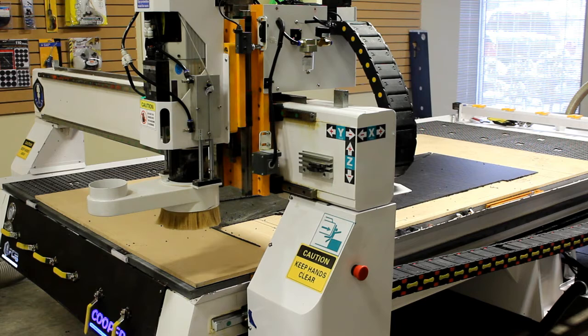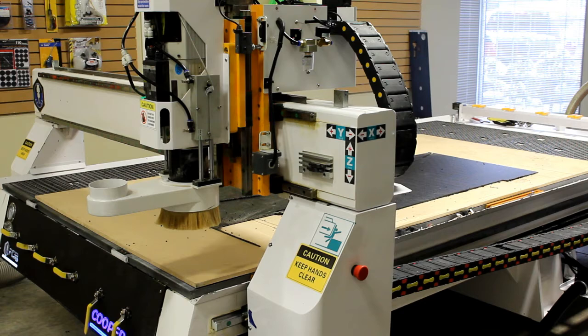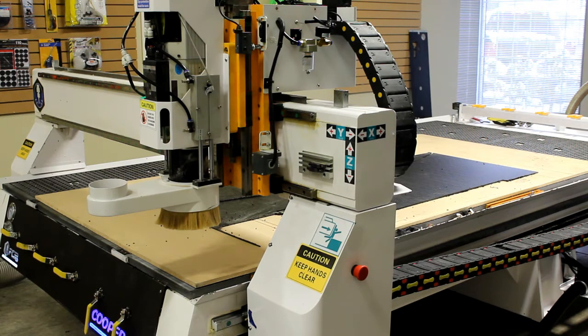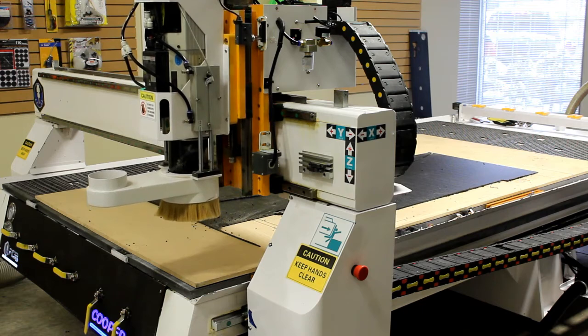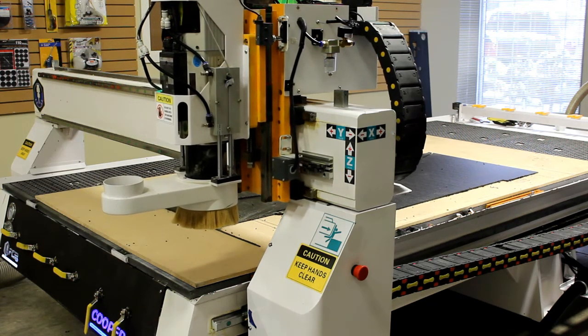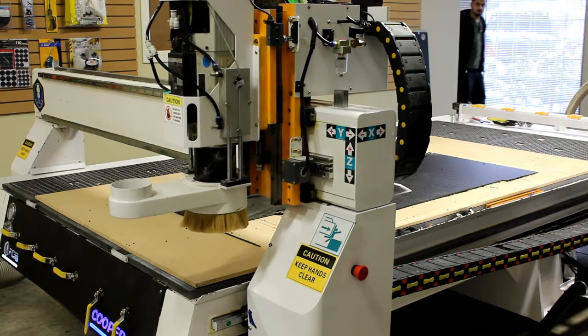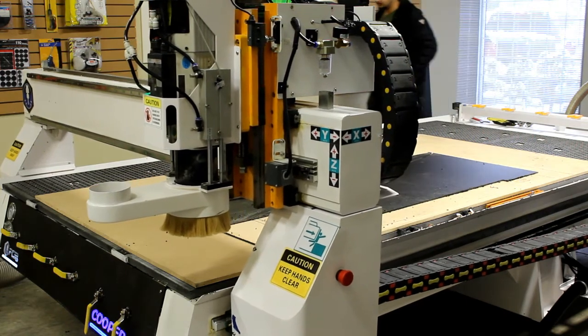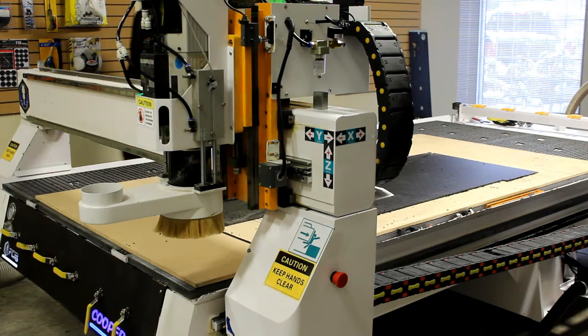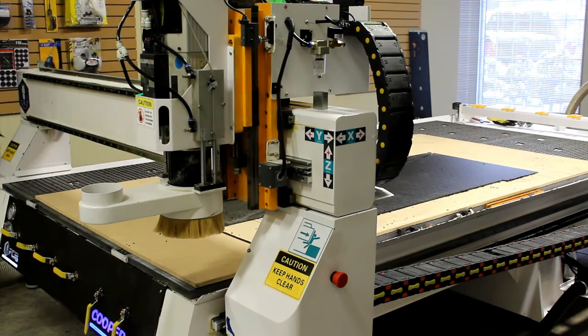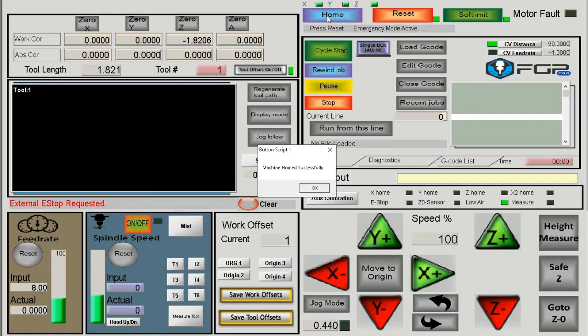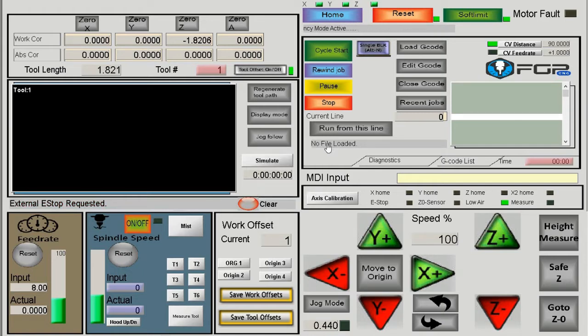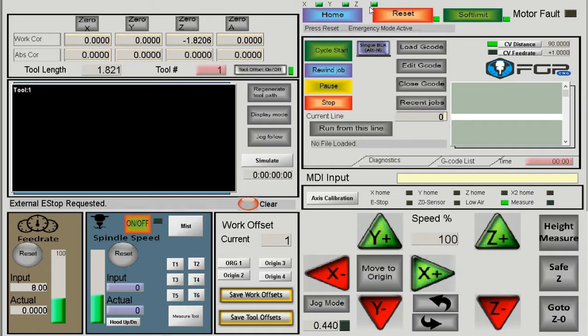When you press home, the machine moves up in the Z direction until it finds the triggering sensor, then moves right, then forward toward the operator, stopping at each sensor. The homing process is slow—about 5 to 10 percent of maximum speed. Because of this, it's best to get the machine close to the home position before pressing home. Once complete, X, Y, and Z indicators all turn green.